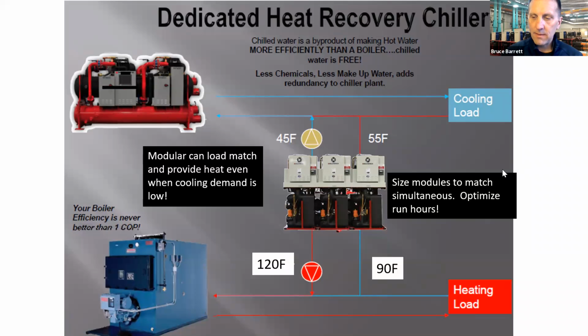Penalty on energy efficiency. The cooling performance will meet 90.1 standards. It's around a 10 EER with a 14 IPLV in air-cooled speak. So it should meet codes, should meet air-cooled chiller efficiency codes. It's going to be interesting to see, because we keep ratcheting up performance requirements. It's going to be interesting to see how AHRI treats this chiller, because it's more than just a chiller. It's also making hot water. And right now, heat recovery chillers are certified in accordance with AHRI standards. There is no standard for heat recovery chillers yet. So it's going to be interesting to see how they treat it, as a chiller or a heat recovery machine.